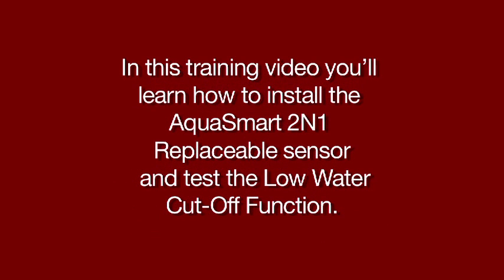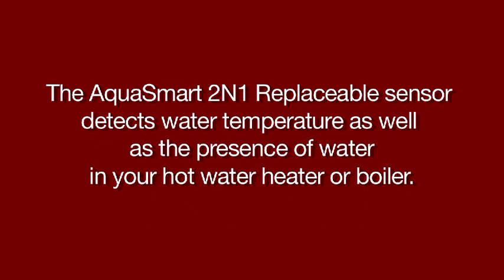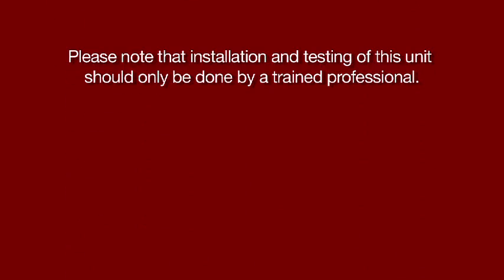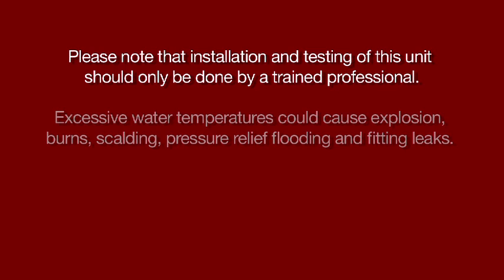In this training video, you'll learn how to install the AquaSmart 2-in-1 replaceable sensor and test the low water cutoff function. The AquaSmart 2-in-1 replaceable sensor detects water temperature as well as the presence of water in your hot water heater or boiler. Please note that installation and testing of this unit should only be done by a trained professional. Excessive water temperatures could cause explosion, burns, scalding, pressure relief flooding, and fitting leaks.